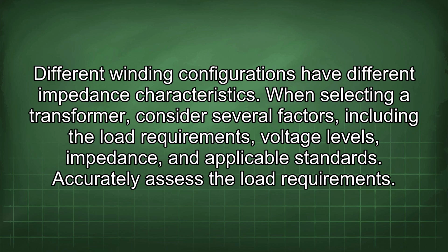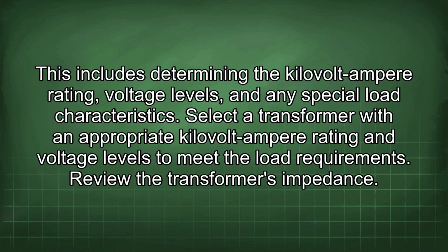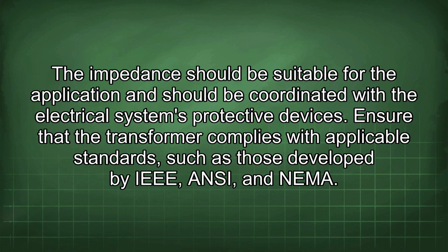When selecting a transformer, consider several factors, including the load requirements, voltage levels, impedance, and applicable standards. Accurately assess the load requirements. This includes determining the kilovolt-ampere rating, voltage levels, and any special load characteristics. Select a transformer with an appropriate kilovolt-ampere rating and voltage levels to meet the load requirements. Review the transformer's impedance. The impedance should be suitable for the application and should be coordinated with the electrical system's protective devices. Ensure that the transformer complies with applicable standards such as those developed by IEEE, ANSI, and NEMA.